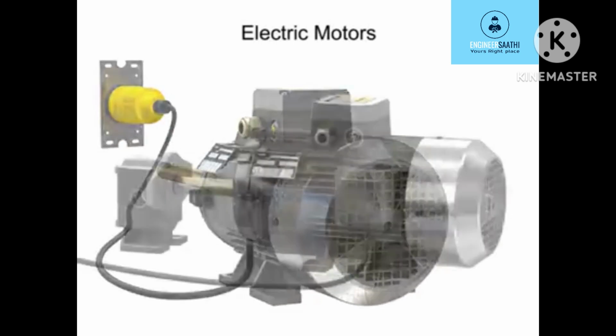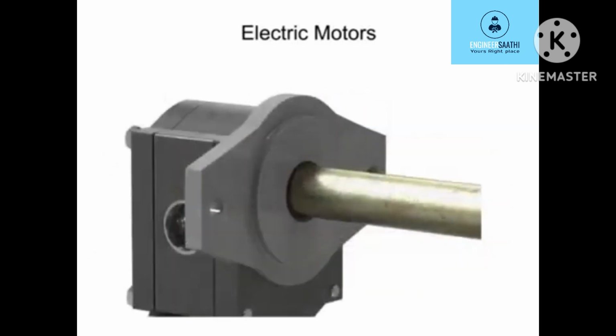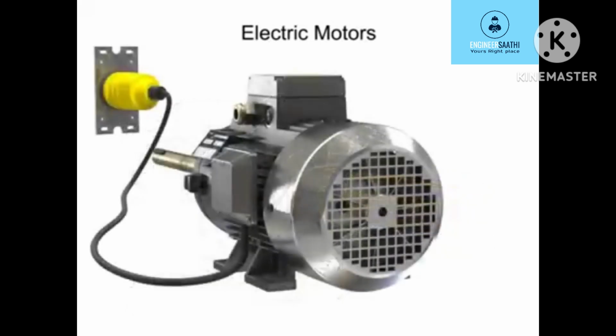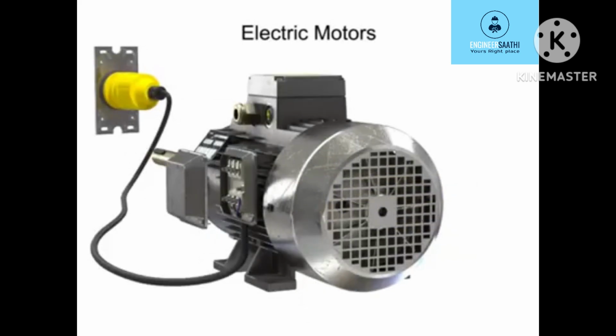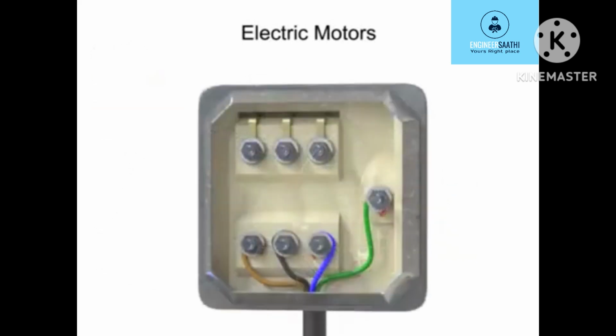For instance, running a pump in the wrong direction may cause damage due to cavitation or expulsion of the shaft seal. If the motor's rotation is incorrect for the required application, it can be reversed by simply interchanging the connections to any two of the three power wires.